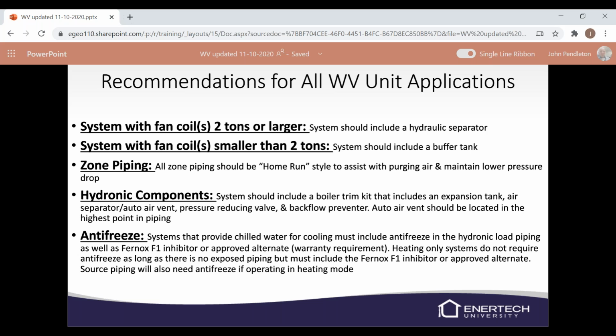Recommendations for the WV unit applications. Systems with fan coils 2 tons and larger, we recommend a hydraulic separator. Systems with fan coils under 2 tons, we recommend using a buffer tank. Zone piping is home run style to assist in purging and maintaining lower pressure drop, and also for servicing.